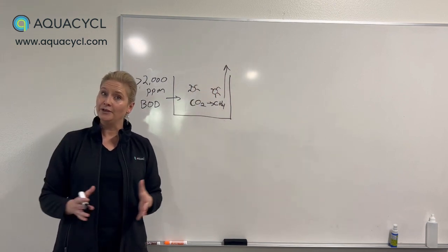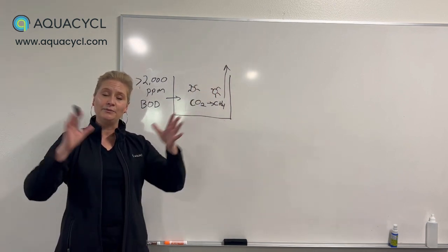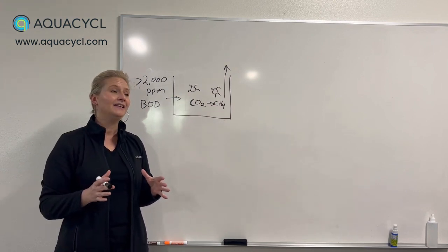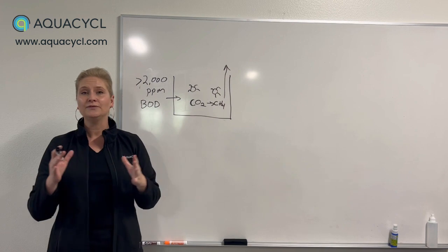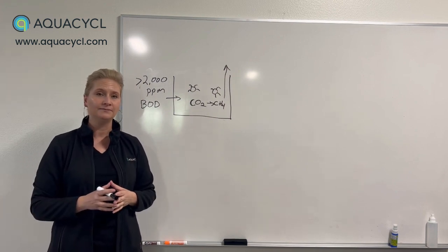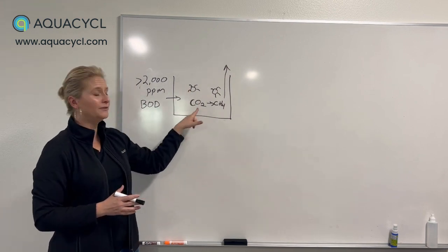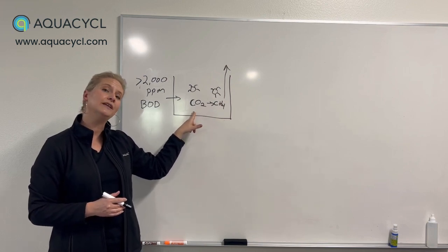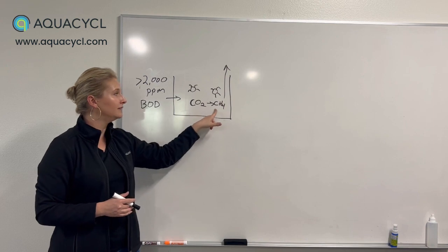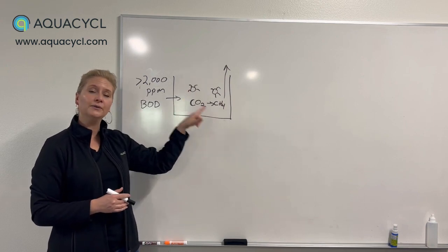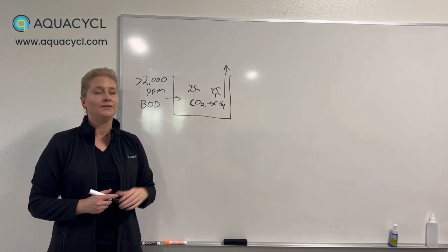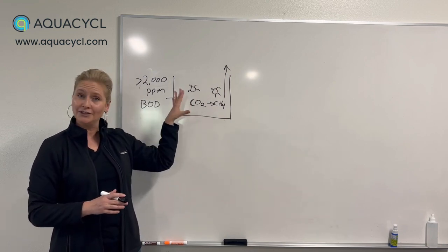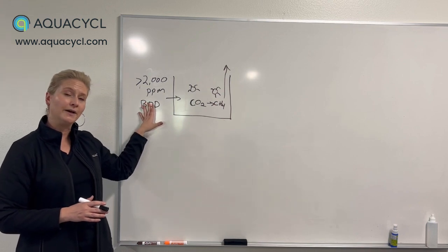But you have to have very good mixing. It has to be heated so the bugs are nice and warm very consistently. And you need to make sure that it's a very even flow of concentration. These organisms are very sensitive to changes in concentration, in temperature, in pH, and variability in the amount of organic load or COD that comes in. They're a little finicky, you gotta treat them real nice, but anaerobic digestion is a good way to go if you've got high concentrate wastewaters.